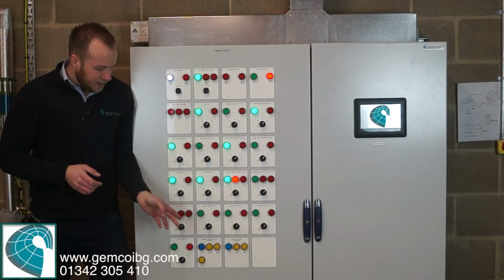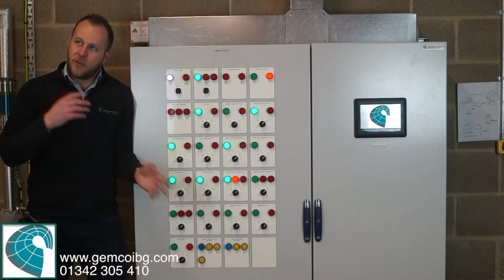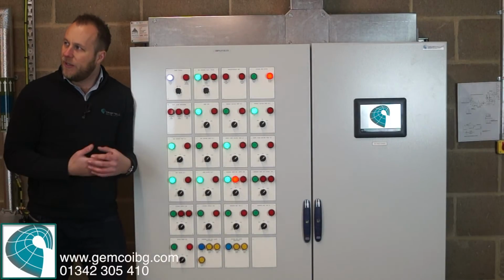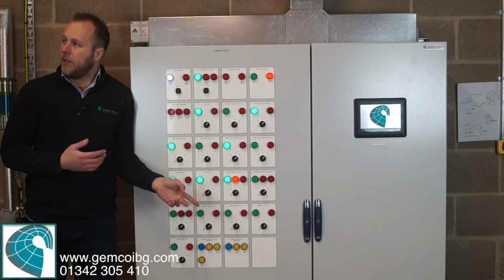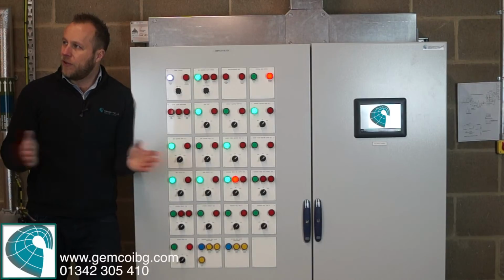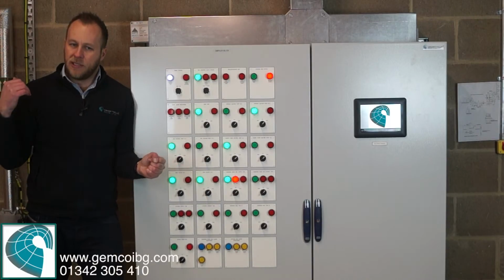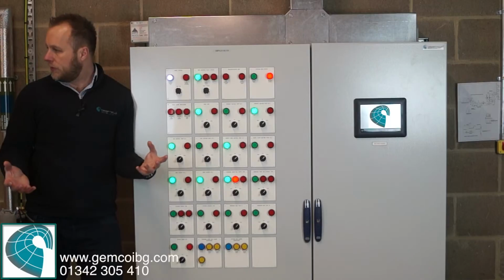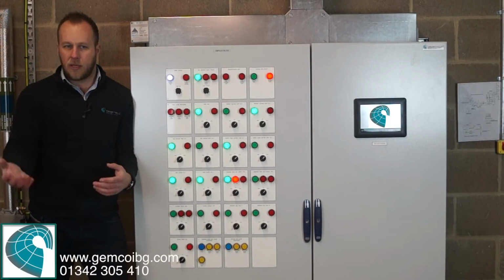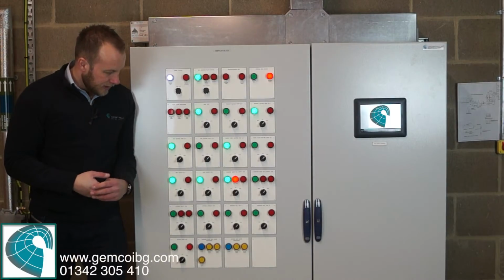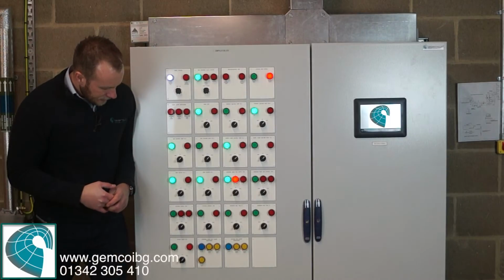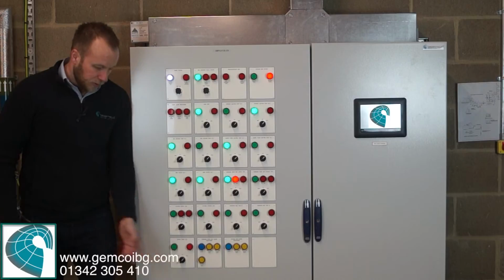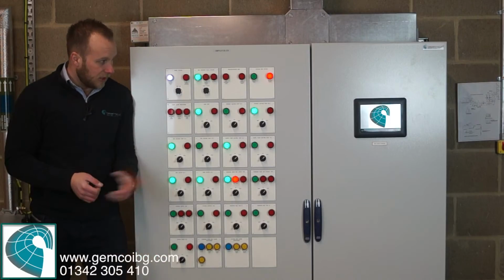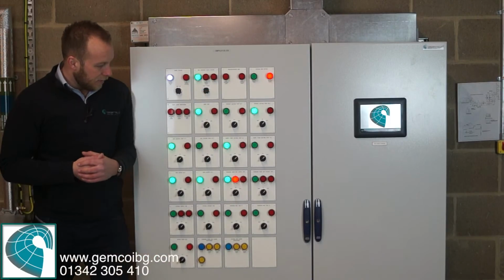Normally with a project like this, where they do all the commissioning and there's dust and stuff, you find that the filters don't last very long in the first few months. But normally, companies like Air, they'll provide you with some spare filters. I don't know if they did that, or they'll just come and replace them because of the dust kicking around during commissioning. And the drying room fan is just on a time switch, which we set in there, and I'll go through that in just a minute.